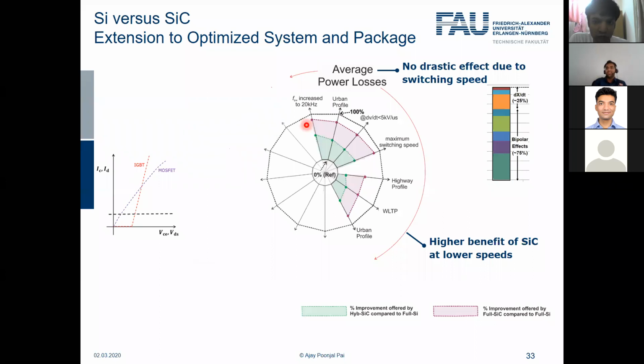I have rarely seen someone switching much higher than that, maybe 12 kilohertz, but not 20, 30 or 40 kilohertz. Why? Because the higher the switching frequency, the higher the switching losses, and it doesn't bring much benefit to the system—only a higher switching loss or lower efficiency. So most OEMs or manufacturers will not go for a higher switching frequency than maybe 12 or 15 kilohertz, and all of this is hard switched.